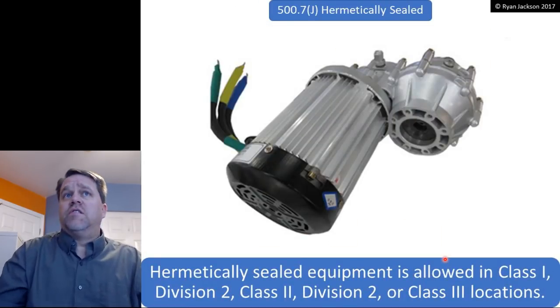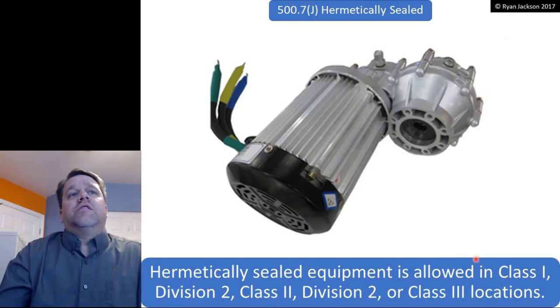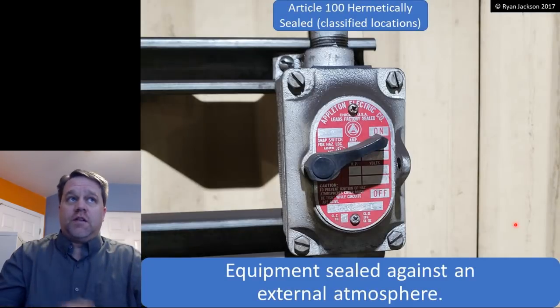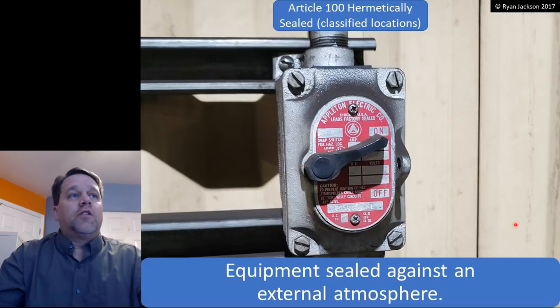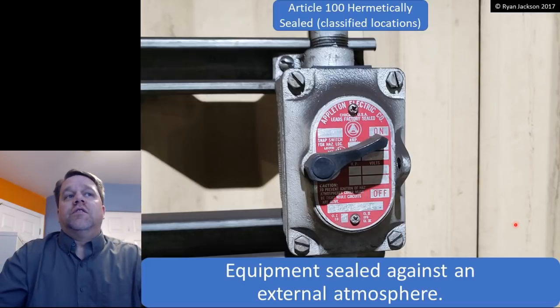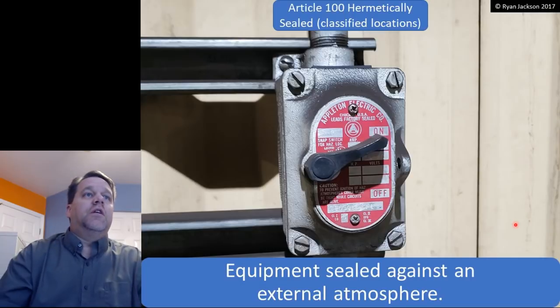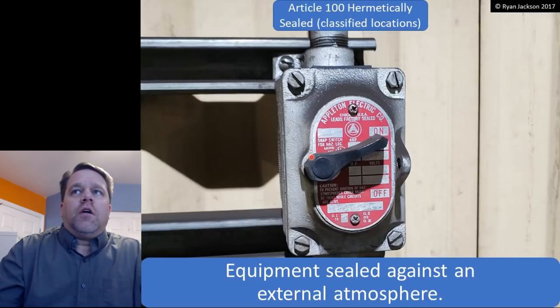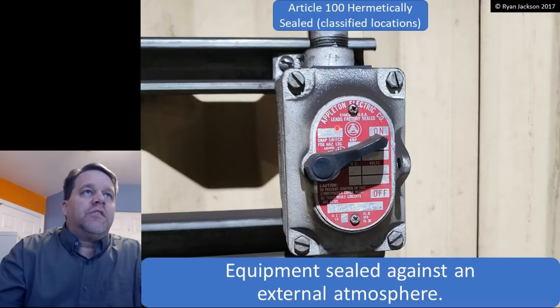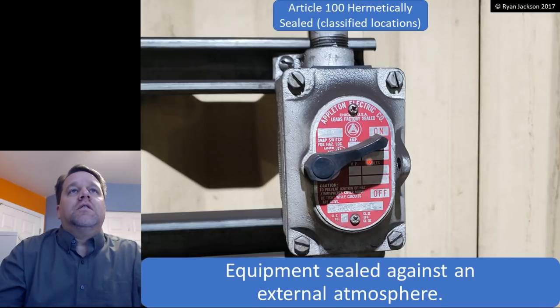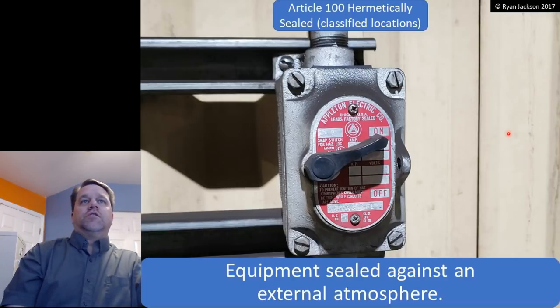Hermetically sealed is another protection technique. That's hermetically sealed is allowed in Class 1 Division 2, Class 2 Division 2, or any Class 3 locations. Hermetically sealed is defined also in Article 100. That's equipment that's sealed against an external atmosphere. It might be a little bit hard to see, but can you see here where it says leads factory sealed? Perfect. This chamber is hermetically sealed. All right, so that is a hermetically sealed enclosure.